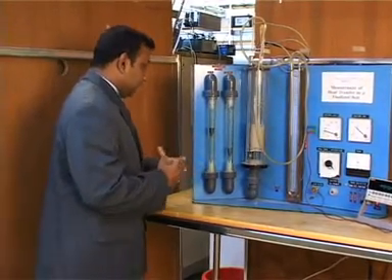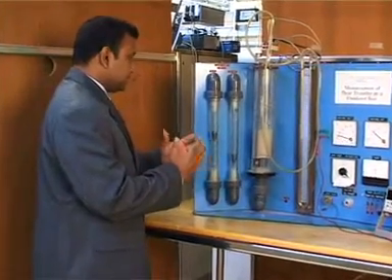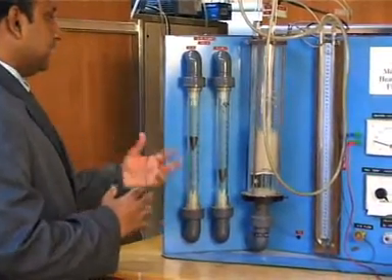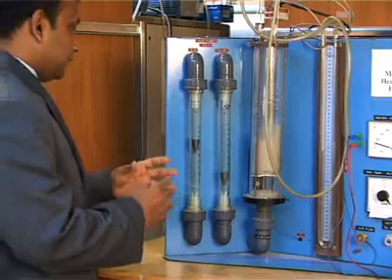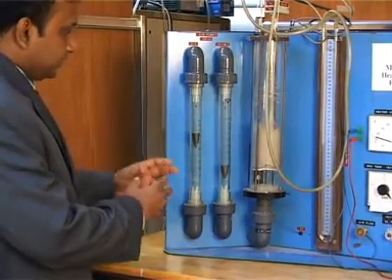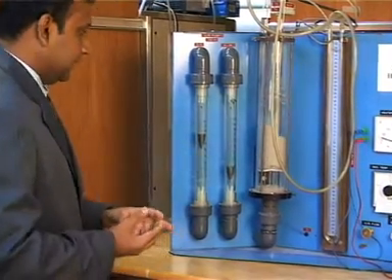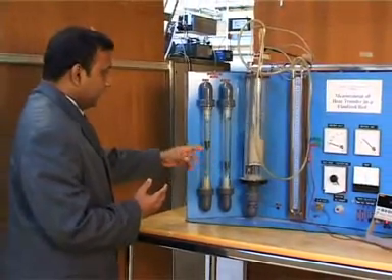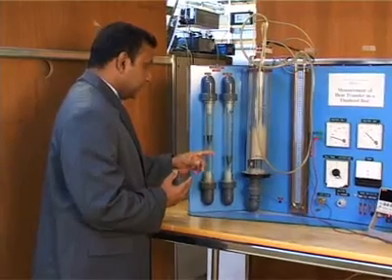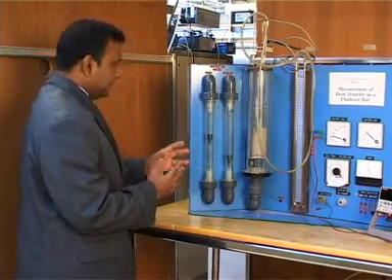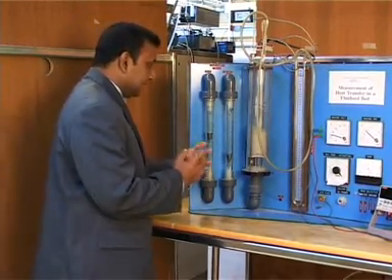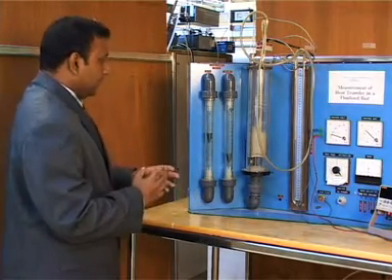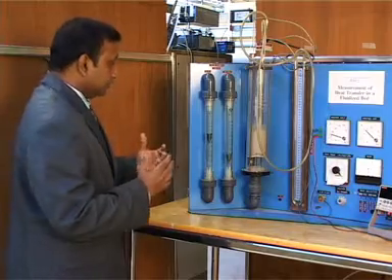So when the fuel is oxidized, it releases heat. That heat will keep increasing the bed temperature. So then, since we need to control the bed temperature, and also we have to extract heat for our industrial process, what we do is we have pipes immersed into the fluidized bed, where those pipes are carrying cooling water, and when the heat is released, the cooling water gets heated, and it generates steam, and that steam will be going into steam plants where we run steam turbines to generate electricity.